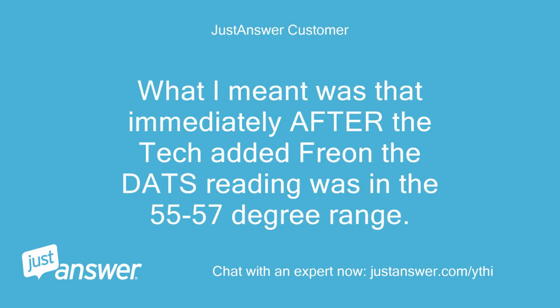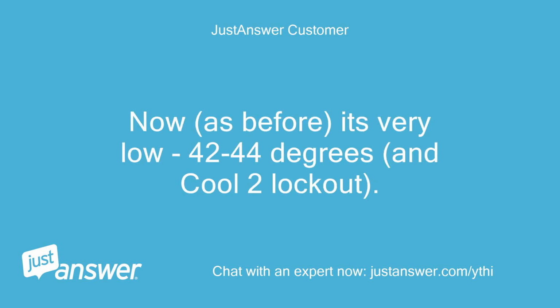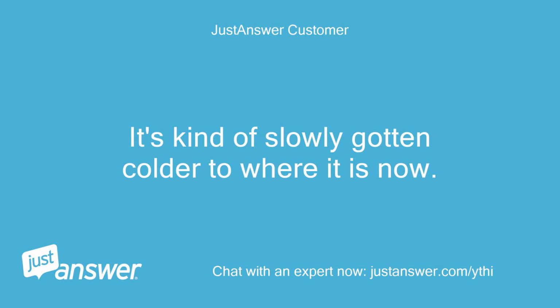What I meant was that immediately after the tech added Freon, the DATS reading was in the 55 to 57 degree range. Now, as before, it's very low, 42 to 44 degrees, and cool 2 lockout. It's kind of slowly gotten colder to where it is now.